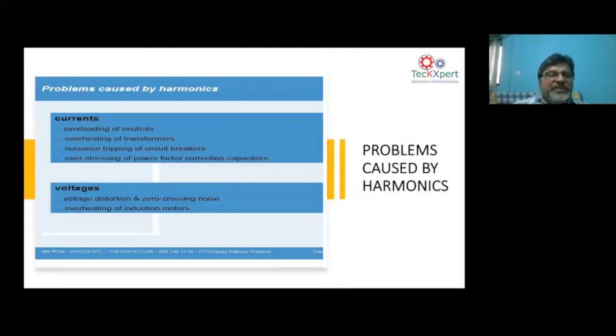Your transformer gets heated because of harmonics. Your transformer no-load losses increase because of the hysteresis losses and eddy current losses, which are proportional to the square of the frequency. Also, harmonics increase the skin effect, which increases the resistance of the cable. So that means your I squared R loss goes up. The impact of harmonics is an increase in all the losses across the network. Your transformer, your cable, everything gets overheated.